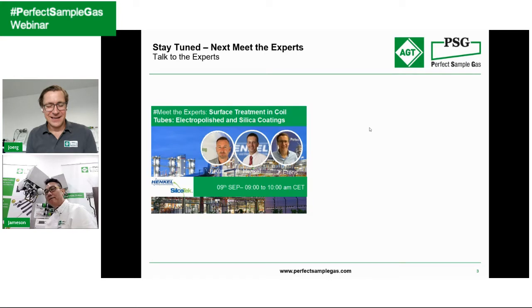We definitely will, especially for the gas analyzer people. All the sample transfer, whether it's to the gas chromatograph measuring small ppm and even ppb, involves memory effects and response time considerations. It's not only gas chromatographs — moisture detectors, infrared, ultraviolet, and many more. As far as analytical extractive systems are concerned, we need a sample transport line, and that's where the technology lies in this transfer.